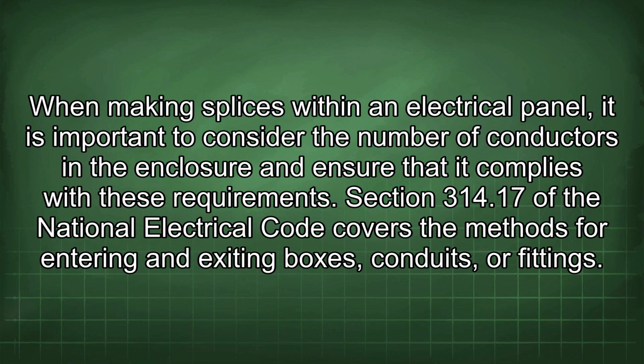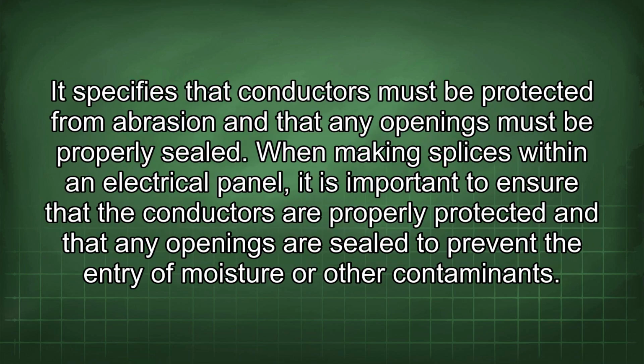Section 314.17 of the National Electrical Code covers the methods for entering and exiting boxes, conduits, or fittings. It specifies that conductors must be protected from abrasion and that any openings must be properly sealed. When making splices within an electrical panel, it is important to ensure that the conductors are properly protected and that any openings are sealed to prevent the entry of moisture or other contaminants.